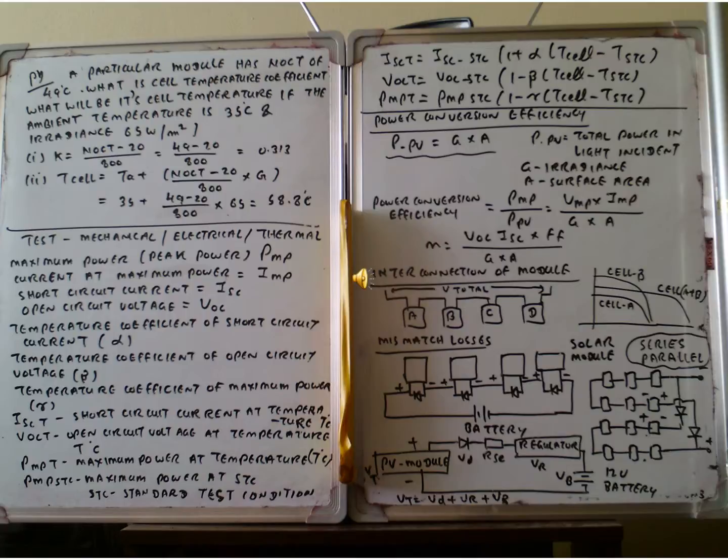So we write down the equation. ISCT is equal to ISC STC multiplying with (1 plus alpha times (T minus TSTC)). And VOCT is equal to VOC STC (1 minus beta times (T minus TSTC)). PMPT is equal to PMP STC (1 minus gamma times (T minus TSTC)). So this is when we get the ISCT, VOCT, and PMPT.